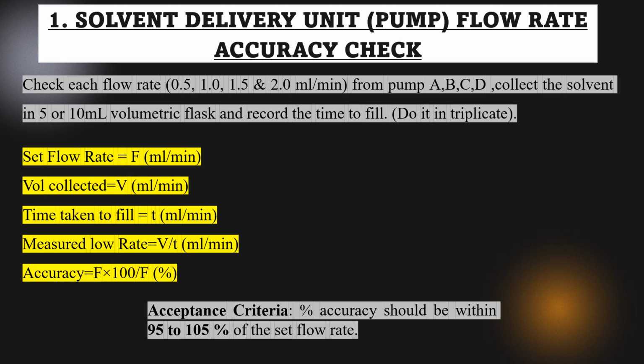When you come to HPLC, the first part that needs to be calibrated is your pump. Now what does the pump do? It pumps the liquid from the mobile phase bottle to the instrument throughout your analysis. Suppose you have given the command to the instrument that the liquid should run at 1 ml per minute. That should be consistent throughout your analysis, or the result that you obtain cannot be relied on. The flow rates that need to be calibrated are 0.5, 1, 1.5 and 2 ml per minute. And there are 4 ports in HPLC, that is port A, B, C, D, so all these ports need to be calibrated.